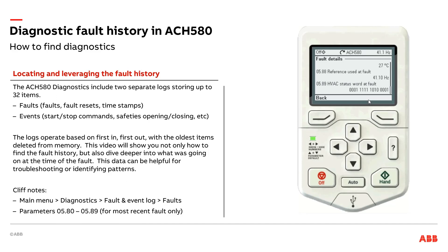Our experienced tech support folks will be able to read this. So this tells me I'm in hand mode, not in off or auto. The next couple of zeros tells me I'm not in override mode, not doing any motor heating. This one here tells me that my damper relay is good to go — it's closed. This zero is reserved. And then the next ones tell me that my run permissive and all my start interlocks are happy. Those are the definitions of those ones and zeros.